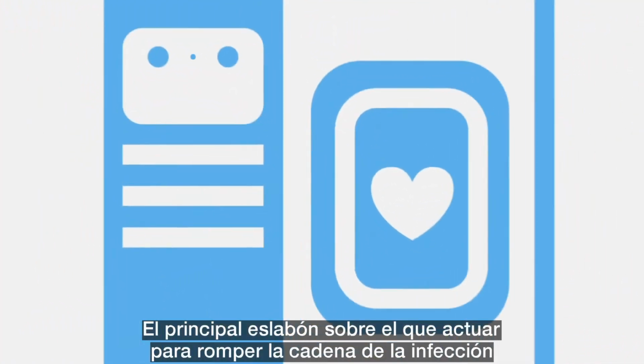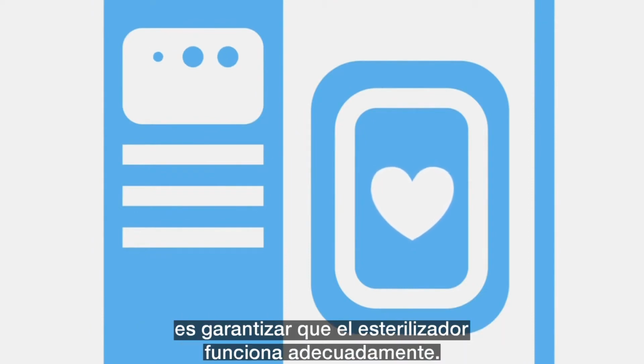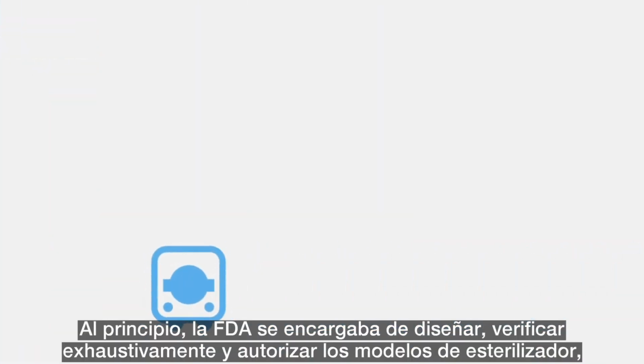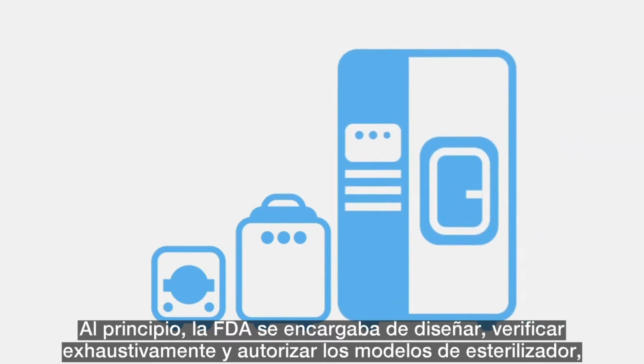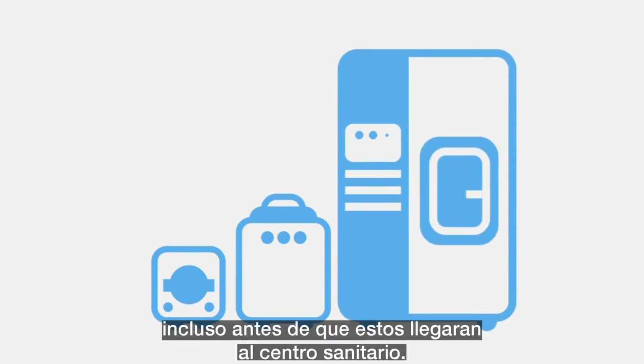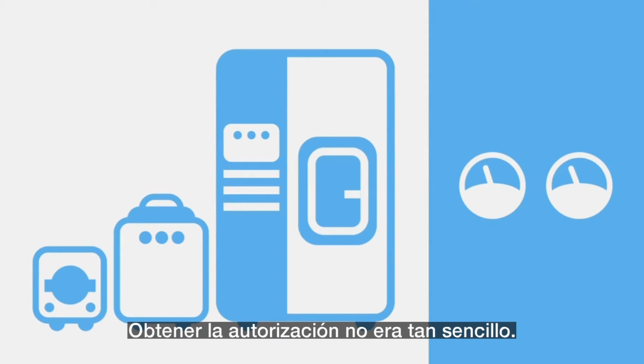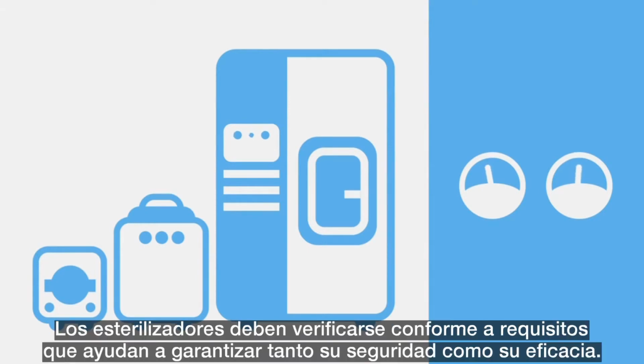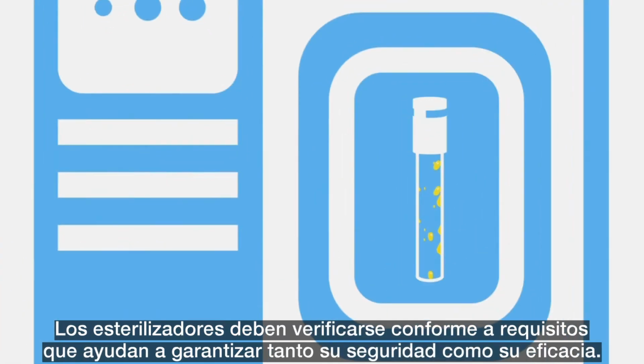One of the most important links in breaking the chain of an infection is to make sure your sterilizer is working properly. In the beginning, before it even arrived at your healthcare facility, a sterilizer model was designed, extensively tested, and cleared by the FDA. Getting clearance wasn't so simple. Sterilizers must be tested against requirements that help ensure both the safety and efficacy of the device.